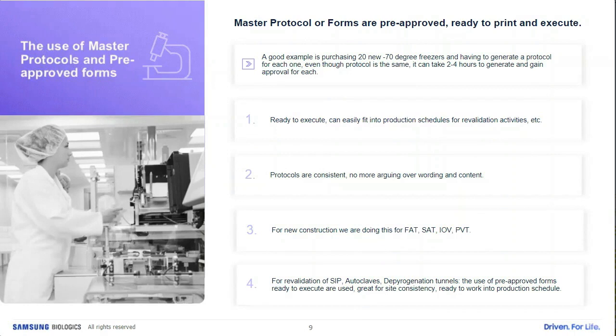The other thing is you could do it by forms. So for each one of those steps, instead of having to generate a protocol, I can have pre-approved forms. If I have a bioreactor and I know I'm going to install thermocouples and do a temperature mapping study with biological indicators, I can have a pre-approved form that has all that information already there. And what I do is just print those forms out and go execute. Again, when you're doing revalidation, that's one of the things that is hard to get into the production schedules, and also to get time with the equipment. So you want to be able to just print these and be ready.